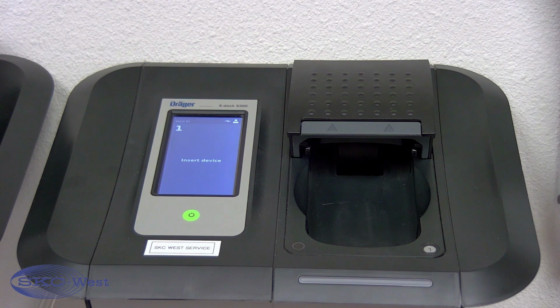If you're having an issue with your X-Dock, most of the time it is due to having low or expired gas. Please check the gauges on the regulators to see if any are low and check the cylinder labels to see if they are expired. If they are, install a new bottle and try again.